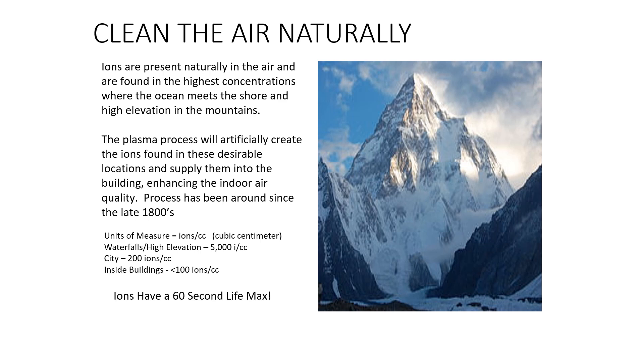If you mount them before the filter, you'll increase filter efficiency a little bit and help sanitize what the filter captures, but you lose the benefit of particle reduction in the space and the benefit of keeping the cooling coils clean downstream. Always mount the technology after the filters. Also, when ions are generated, you have about 60 seconds of life. So if the technology is mounted in the air handler and your ductwork velocity is 1,000 feet per minute, you can determine how many feet of ductwork you have and approximately how many ions will reach the space. Knowing the velocity and duct length, you can determine the overall capacity into the space.